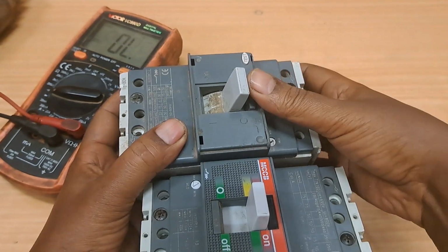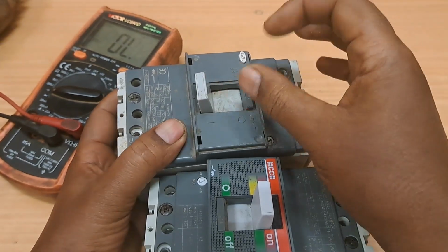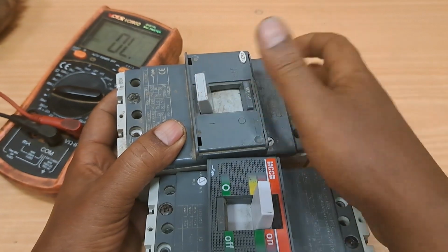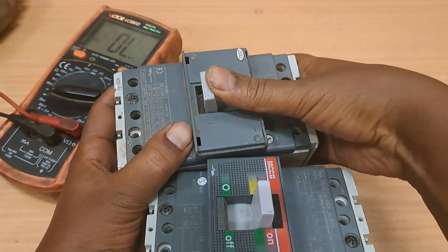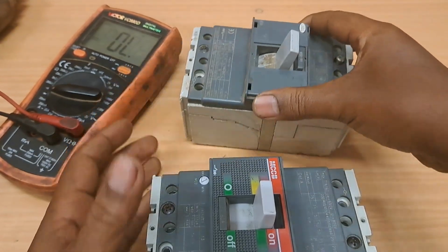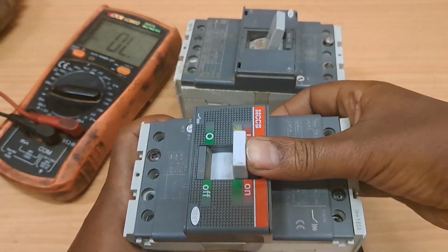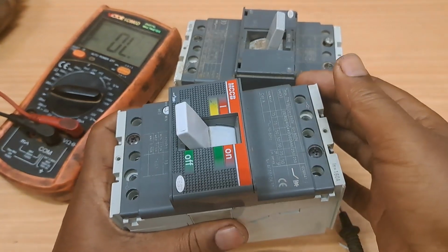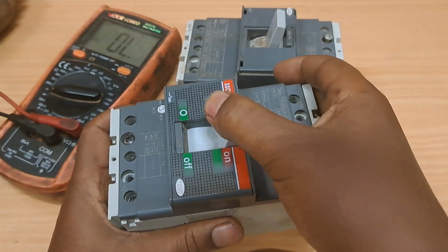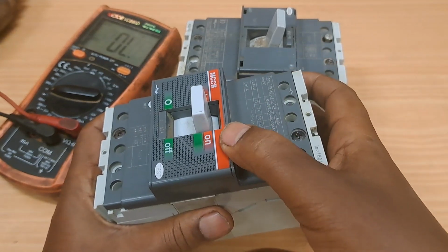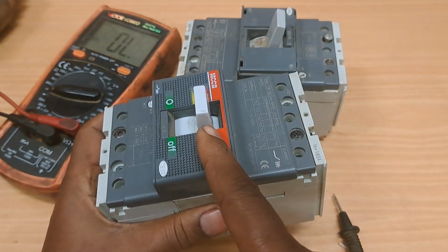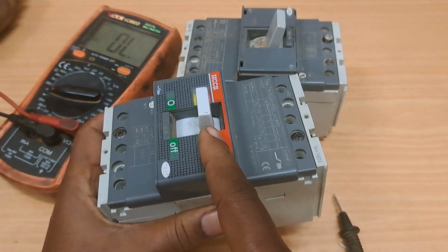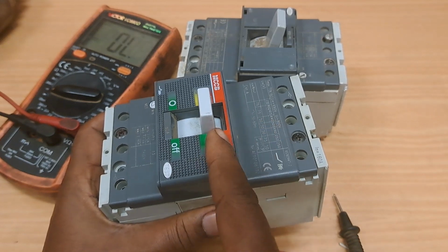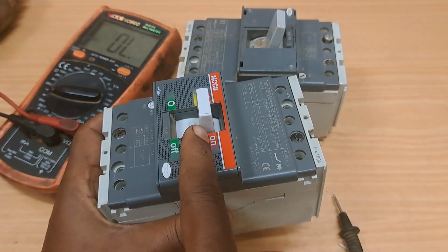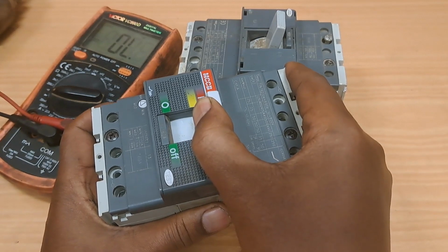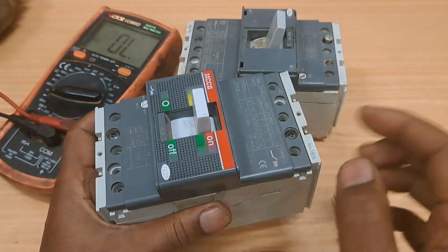See, this is when the spring is keeping the contacts closed and keeping them separated. There has to be a strong latching sound of this kind. But when it comes to right here, there is no such thing. When turned to off, it simply slides. When placed to the on position, it is not reaching the on position, rather it is remaining in the trip position. This is where it comes when current passes through and the breaker trips. When it is on, it was supposed to go the full length, but now it is not there.